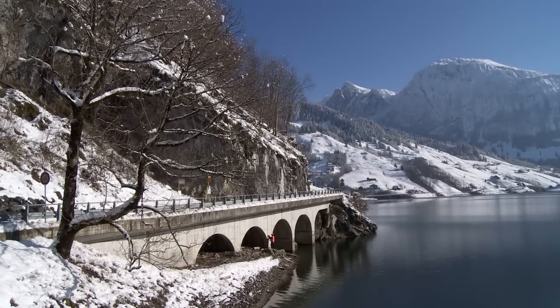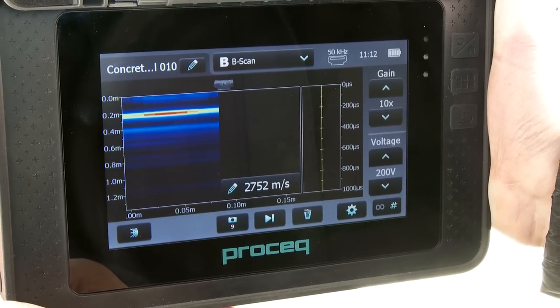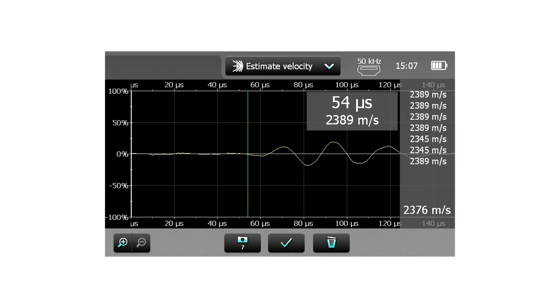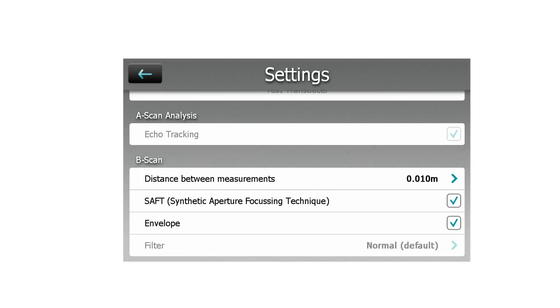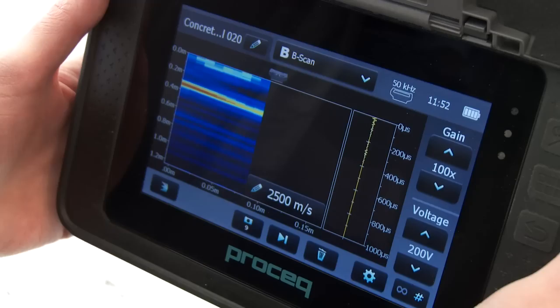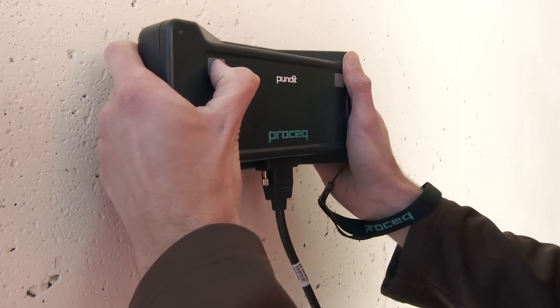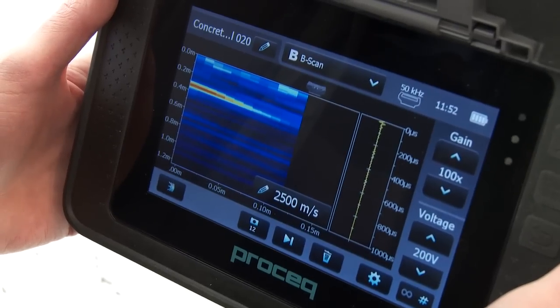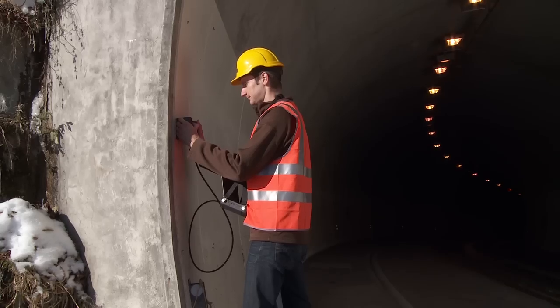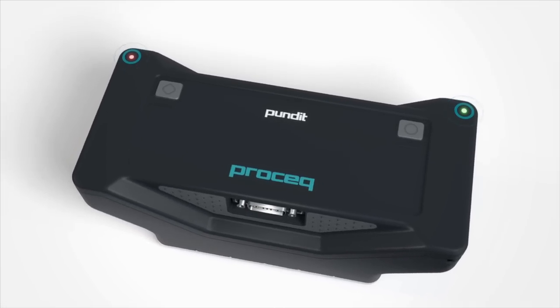The measurement process is greatly assisted by Proceq innovations such as the advanced echo tracking technology, which helps identifying the main echo and the automatic estimation of the pulse velocity. User-definable digital filters provide better echo visibility and noise suppression. The real-time B-scan mode provides a cross-sectional view perpendicular to the scanning surface. Powerful image processing software improves the image quality, facilitating the search for pipes, cracks, voids and more. Control buttons and optical feedback directly on the probe increase the measurement efficiency.